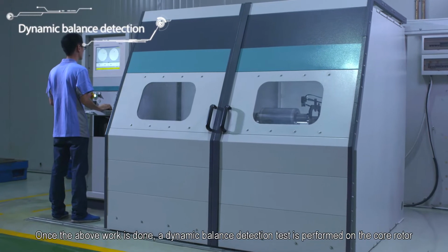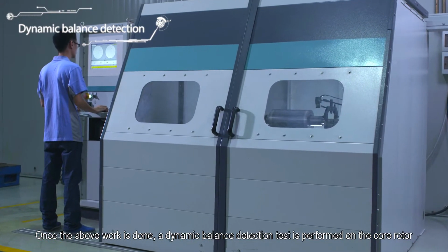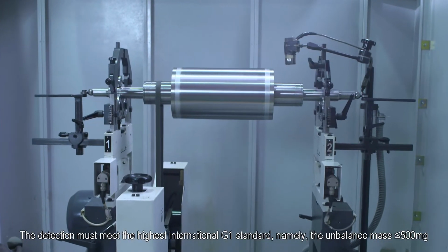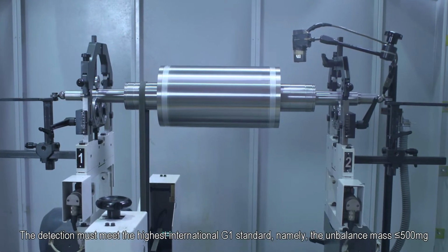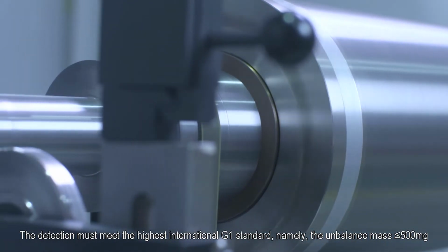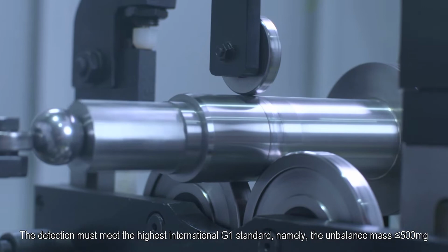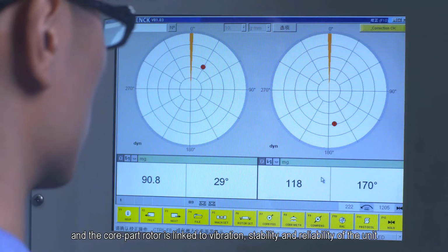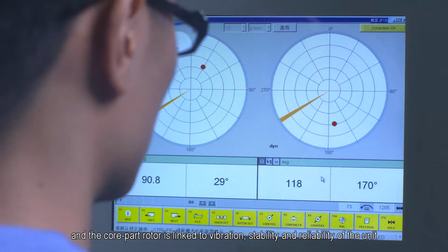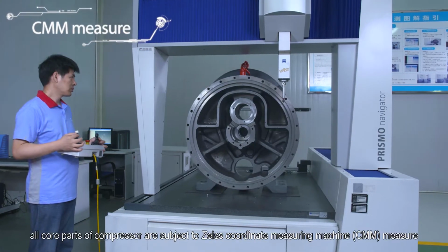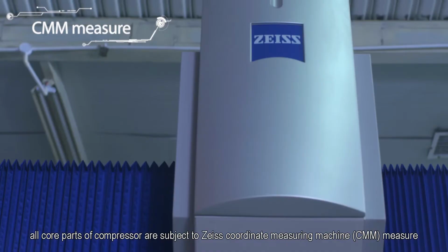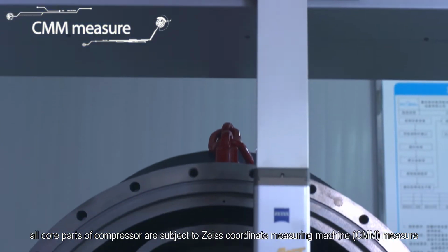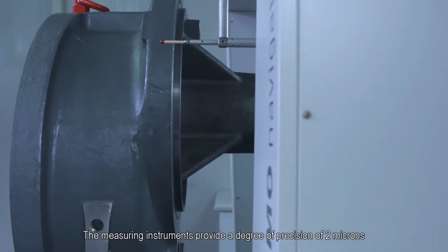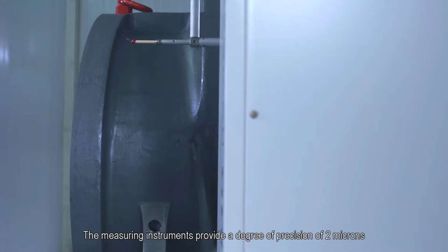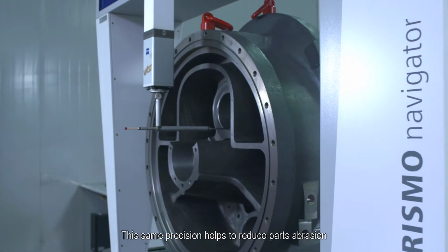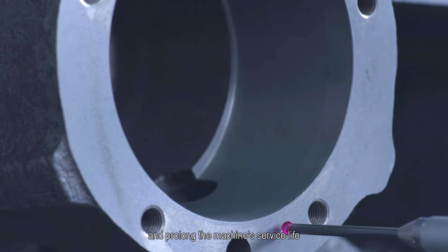Once the above work is done, a dynamic balance detection test is performed on the core rotor. The detection must meet the highest international G1 standard, namely, the unbalanced mass less than or equal to 500 milligrams, and the core part rotor is linked to vibration, stability, and reliability of the unit. Balance detection. In addition, all core parts of a compressor are subject to Zeiss coordinate measuring machine (CMM) measurement. The measuring instruments provide a degree of precision of 2 microns. This same precision helps to reduce parts abrasion and prolong the machine's service life.